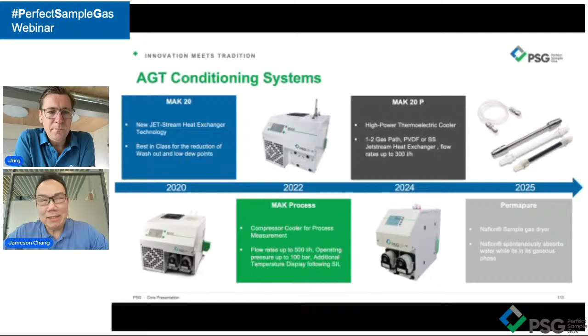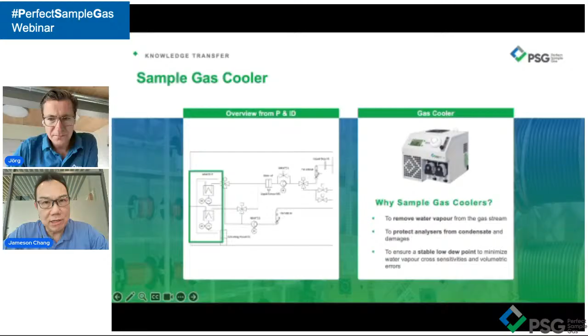Wow, I think this is a very interesting question, right? When I'm selling and promoting the gas cooler, it again goes back to the inlet dew point and outlet dew point. In the entire gas sampling for emission monitoring, when we want a robust sampling system, why the probe is 180 degrees, why the heated line is 180 degrees, why the cooler is 3 degrees, we only address one thing: dew point, just a dew point.